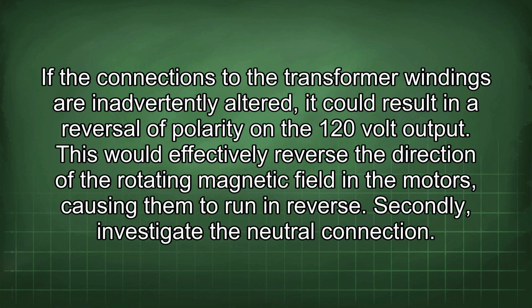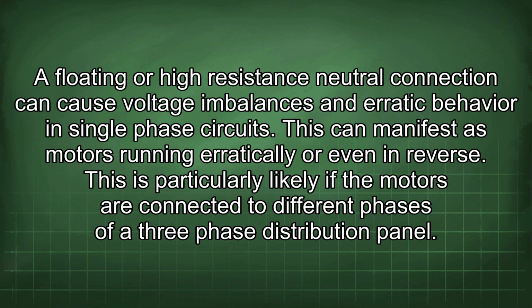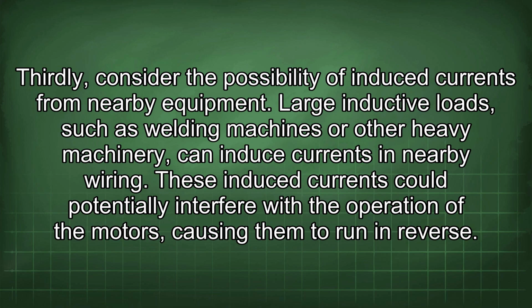Secondly, investigate the neutral connection. A floating or high-resistance neutral connection can cause voltage imbalances and erratic behavior in single-phase circuits. This can manifest as motors running erratically or even in reverse. This is particularly likely if the motors are connected to different phases of a three-phase distribution panel. Thirdly, consider the possibility of induced currents from nearby equipment. Large inductive loads, such as welding machines or other heavy machinery, can induce currents in nearby wiring. These induced currents could potentially interfere with the operation of the motors, causing them to run in reverse.